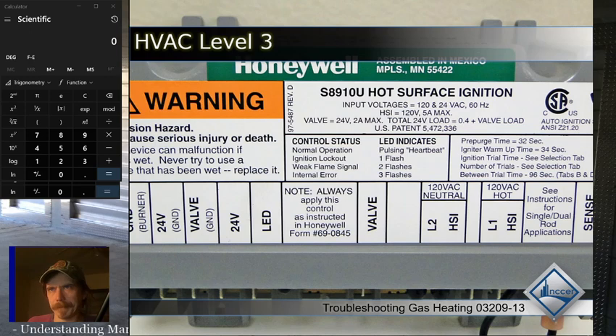So that's kind of what they'll ask you on your test: which way does it have to be to see if it's leaking? If it's in the right mode, you won't know you have a leaking check valve until you switch modes. Okay? So the check valve should be open on the outdoor unit in cooling, and it should be open on the indoor unit in heating. It should always be closed for the opposite mode.